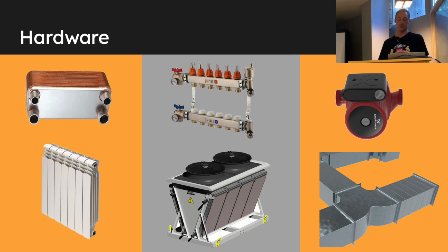So this would be more for not reusing the heat, but rejecting the heat. What this does, it's like the radiator, but it's just a bunch of tubes with many, many more fins and then fans on top that ramp up and down to force air through it. It's called forced convection. And that's how most large-scale Bitcoin miners right now reject that heat.